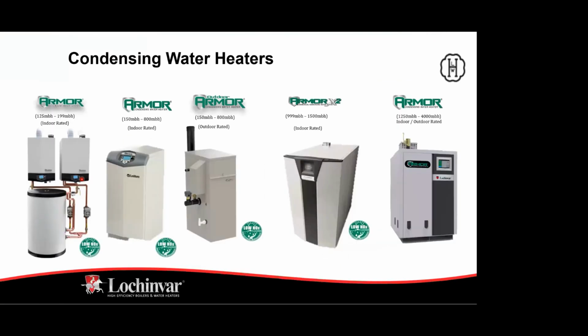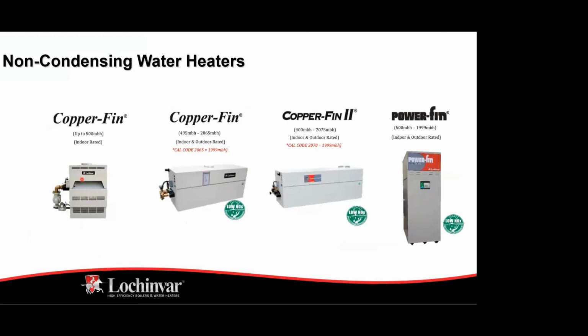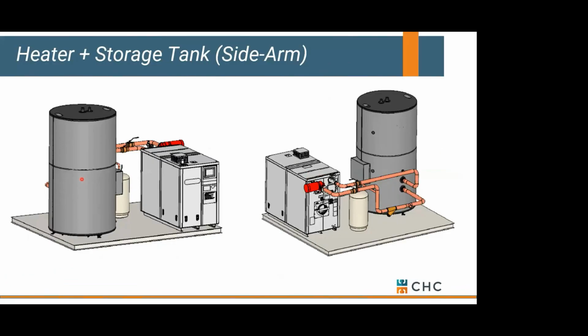You've got different choices for water heaters or sidearm dedicated water heaters. Condensing is one option that's out there for sure, and the other is going to be a non-condensing option. One thing we have to think about is if we're storing this storage tank at 140 degrees, what temperature are we going to expect coming out of the bottom of it anytime the heater fires to recover the storage tank?